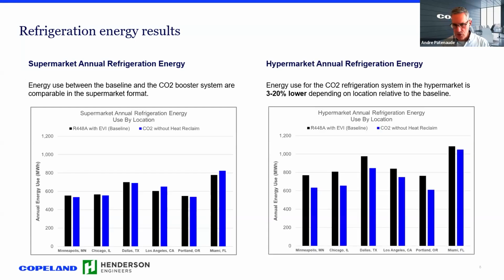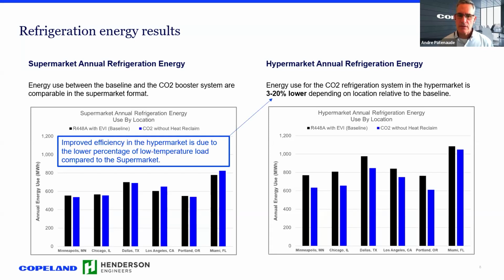Now, if we go to the next one, which is hypermarket, you'll see that the bars look quite different. The hypermarket is about 3 to 20% lower for CO2 energy. And you can see Minneapolis, Chicago, Dallas, they're all lower. Miami, just marginally lower. Again, this does not include heat reclaim. And if you click the next build, please, Trevor, it's all about that difference in percentage of low temp to total load. The supermarkets was higher, as I mentioned, 35%. The hypermarket was a little bit lower.